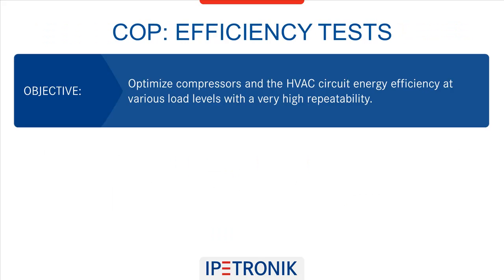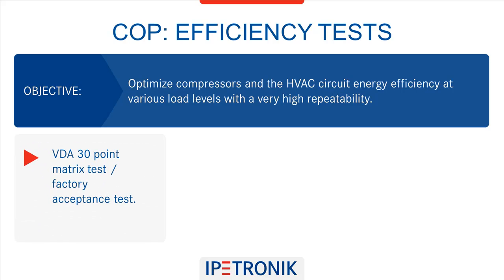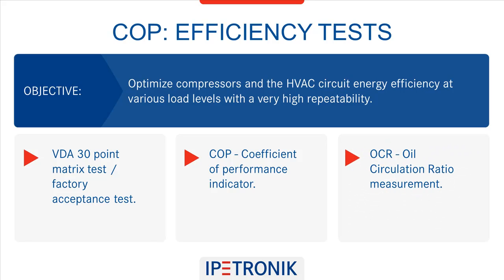The efficiency tests put the focus on design validation of different prototypes. These tests are similar to 30-point matrix testing, measuring compressor efficiency and performance at defined mass flow, temperature, and pressure levels. The COP, coefficient of performance, is a very important test, indicating the energy balance between overall power consumption and cooling output. Another key indicator is the OCR, oil circulation ratio, which will be explained on the next slide.